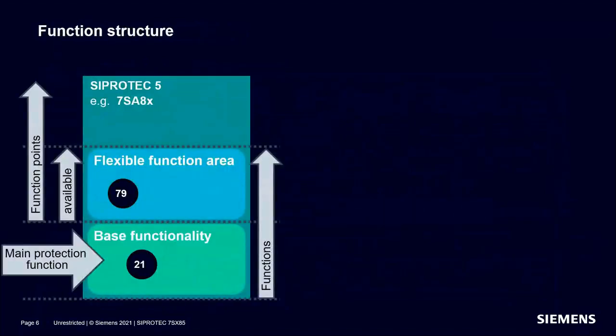In the type-related SIPROTEC 5 relays, we have so-called main protection functions, like a distance protection function, already together with additional functions like teleprotection or emergency overcurrent protection in the basic package. Additional functions like auto reclosure can be added in a flexible function area.